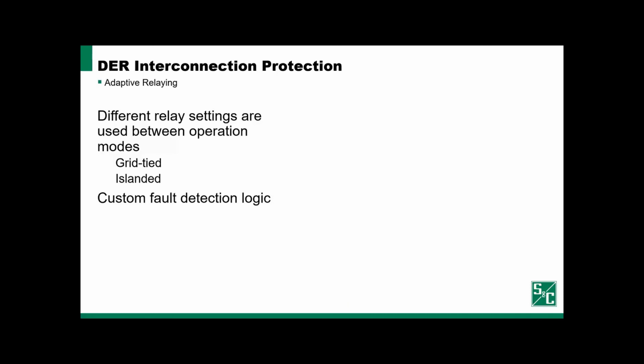Another technique and approach that we can use to protect DER penetrated and microgrid systems is adaptive relaying. There are many different forms of adaptive relaying. The two major forms are either pre-selected settings groups or on-the-fly adjusted protection settings. My personal preference is towards pre-calculated settings groups that we have defined and are confident will protect the system through the modes of operation we're expecting. This can be easily identified in microgrid systems where we have a significant difference between grid-tied and islanded behavior. We use this in tandem with custom fault detection logic as well to ensure that we're detecting faults accurately, sensitively, securely and reliably.